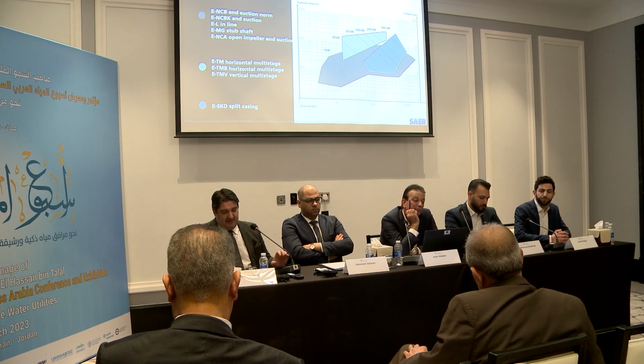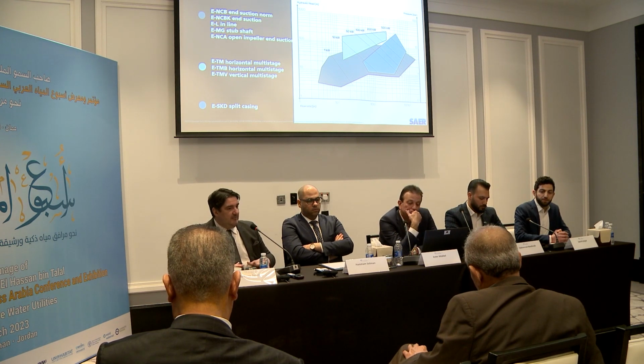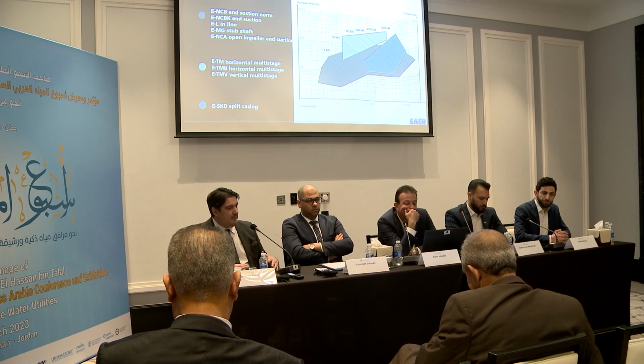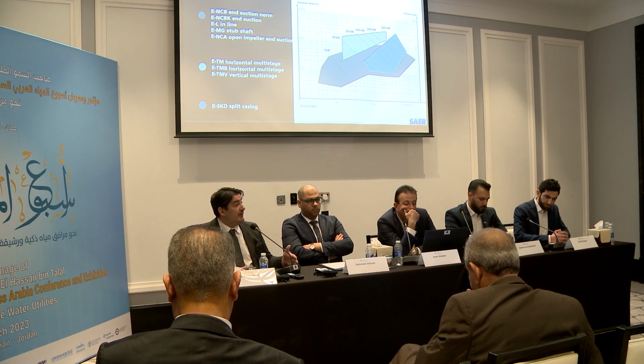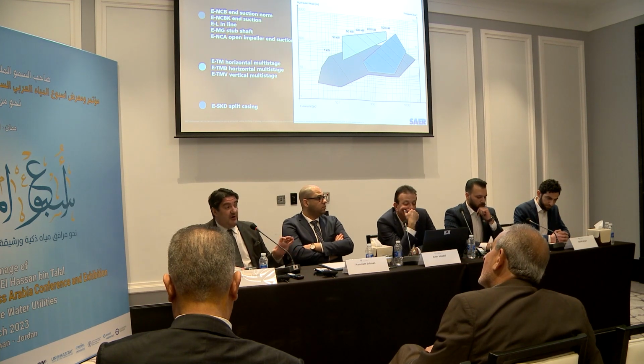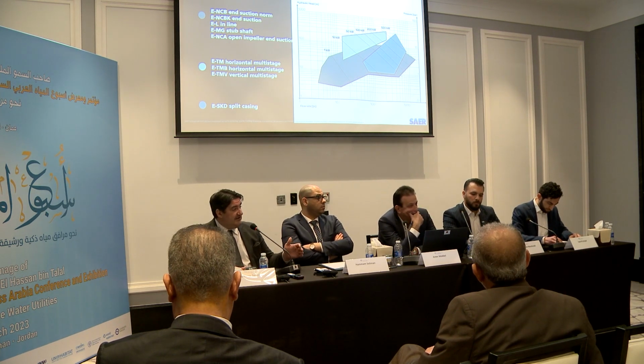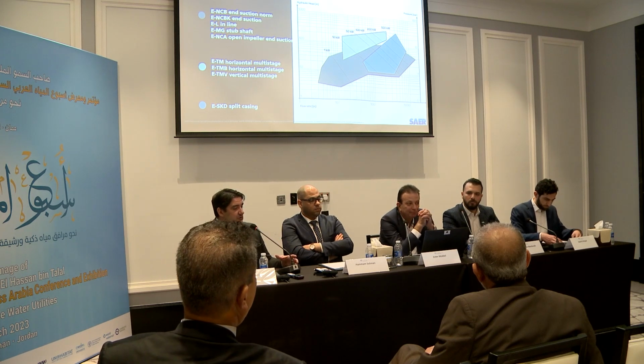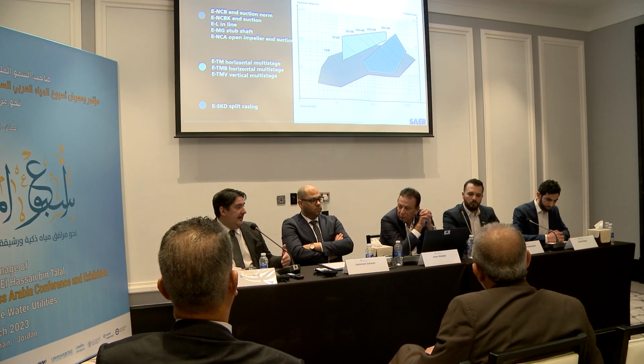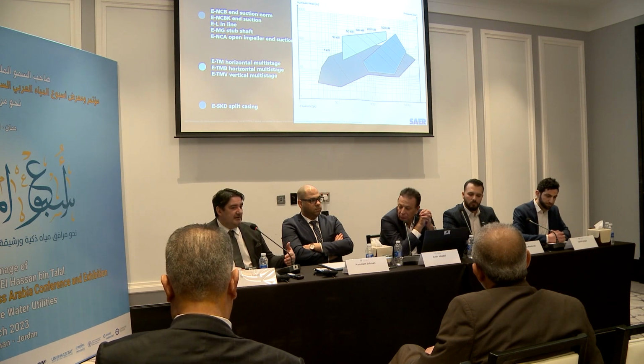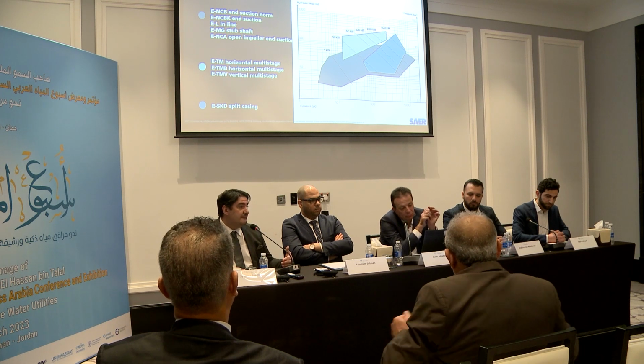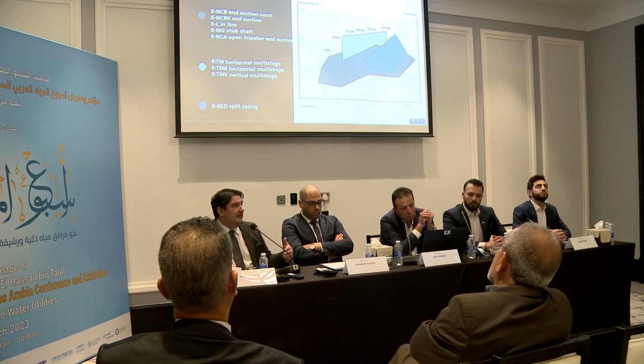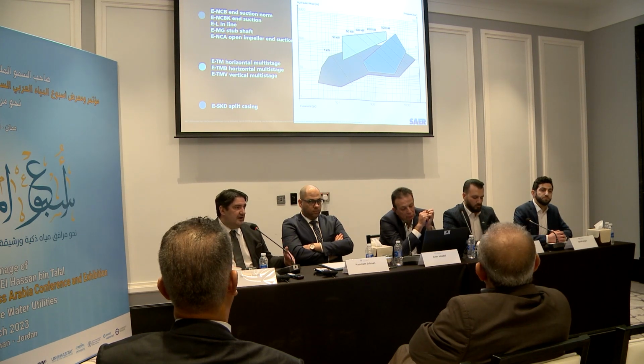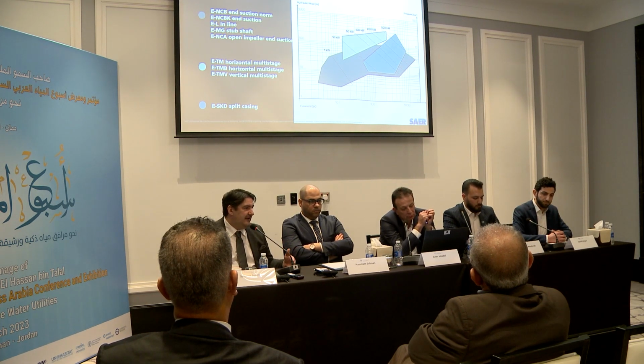Another interesting and important thing is the material of construction, because we have our range of pump as turbine made in different materials, not only cast iron, but also stainless steel and super duplex. Why could it be very important to have stainless steel and super duplex available? Because this kind of system could be used also with seawater. Every day it is more important in the world to use seawater, for example for the production of potable water, and it's very common to use seawater or salty water also for industrial plants.